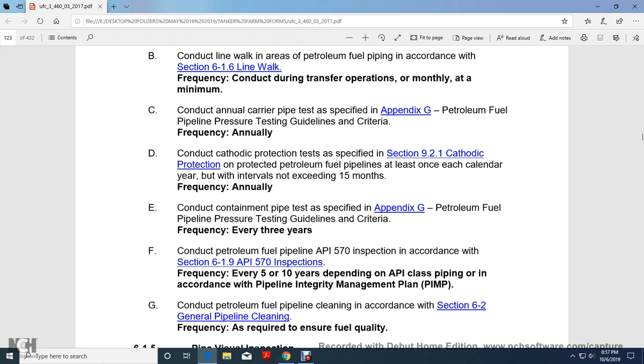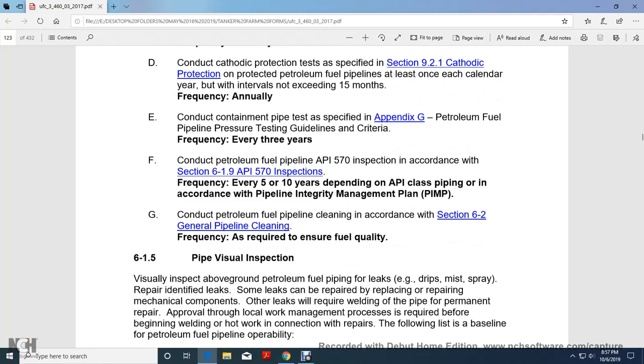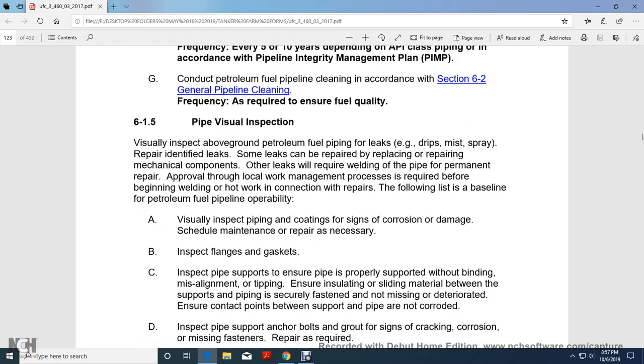Conduct the containment pipe test in Appendix G, Petroleum Fuel Pipeline Pressure Testing Guidelines, criteria every 3 years. Conduct the petroleum fuel pipeline API 570 inspection in accordance with 6.19, API 570 Inspection, every 5 to 10 years depending on the API classification, in accordance with the pipeline integrity management plan. Conduct petroleum fuel pipeline cleaning in accordance with 6.2, General Pipeline Cleaning, frequency as required to ensure fuel quality.